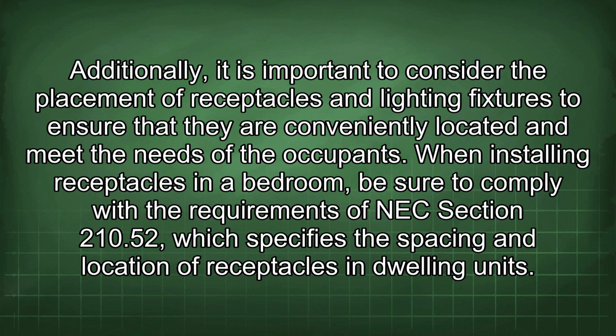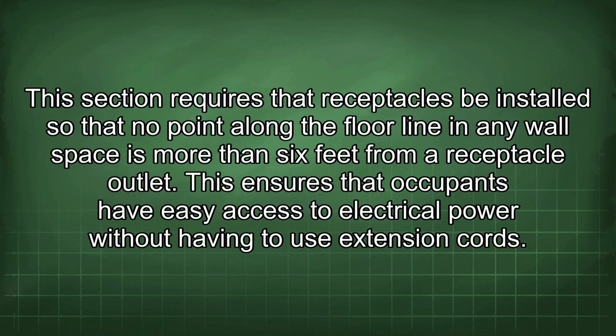When installing receptacles in a bedroom, be sure to comply with the requirements of NEC Section 210.52, which specifies the spacing and location of receptacles in dwelling units. This section requires that receptacles be installed so that no point along the floor line in any wall space is more than 6 feet from a receptacle outlet. This ensures that occupants have easy access to electrical power without having to use extension cords.